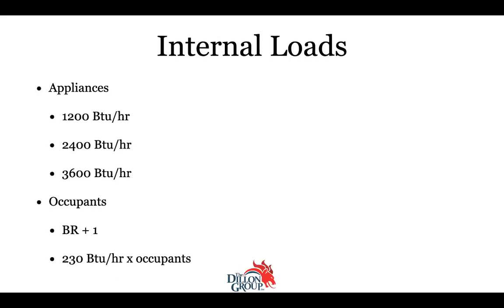And then 3600 BTUs per hour. Again, it's a bigger house. And that's the guidance they give in Manual J. Use this load if the house is this size, use this load if it's this size. It's based on the square footage, I think, and number of bedrooms, because that gives you a nice sense of how many times people are going to be doing laundry, that kind of thing. And then the occupants, Manual J has always had number of bedrooms plus one, because you always assume there are two people in the master.